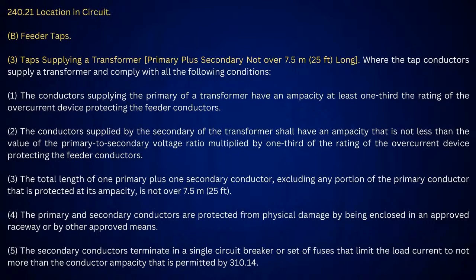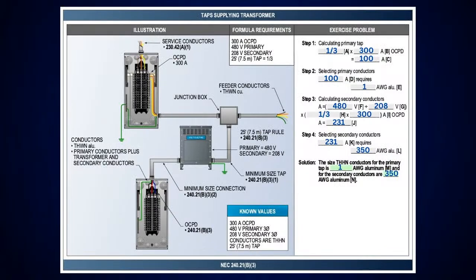Okay. So it's a question for you. Is there any length on the primary tap on that? Because it says 25 foot long, but it's taps supplying the... But if it's outdoor, it's all within 25 foot. That's why for outdoor, it says primary plus secondary not over 25 foot. Oh, gotcha. And then after you come off that secondary, you go, of course, as long as you need to. All right, gotcha.